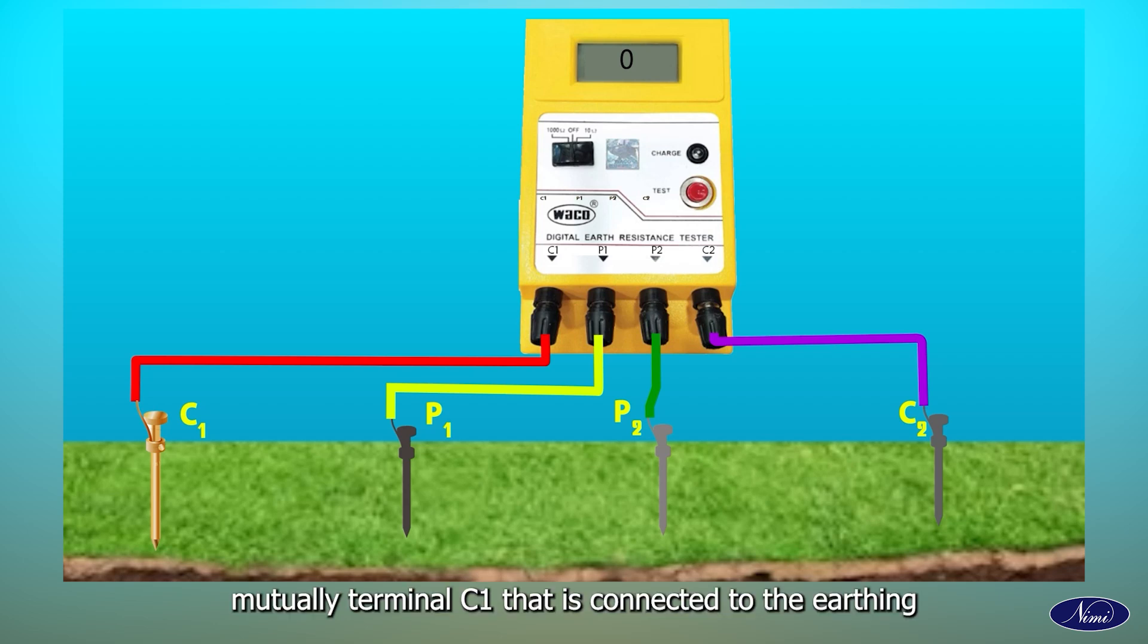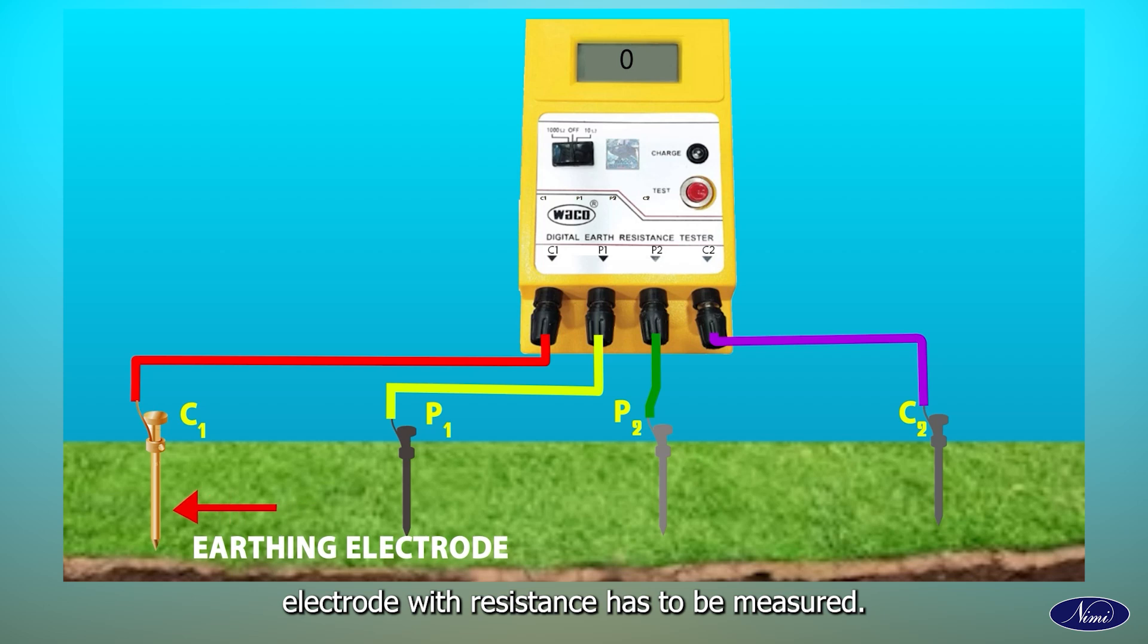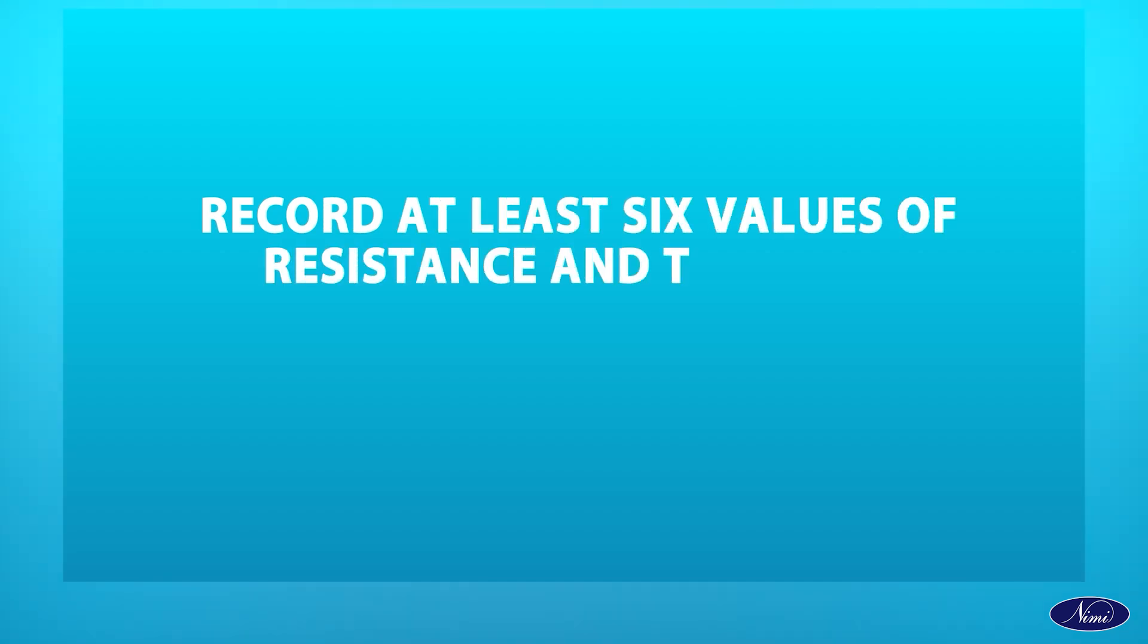Usually, terminal C1 is connected to the earthing electrode whose resistance has to be measured. Press TEST on the Earth Resistance Tester to test the resistance. Record at least six values of resistance and take the average as the exact value of the resistance measured.